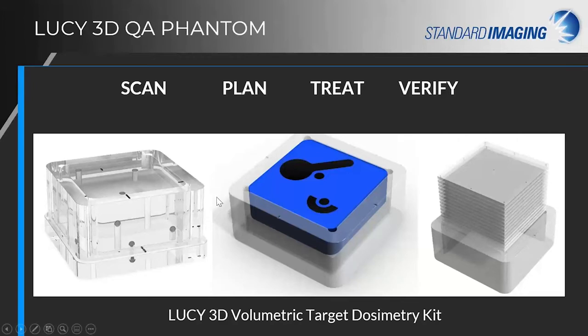One of the things that we do at Standard Imaging is look at what the challenges are on the market. We have customers, and OEM manufacturers such as BrainLab and Accuray or Varian Elekta have particular needs. For example, with the multi-mets insert, a customer says, hey, I want to use BrainLab's Elements software, but I don't know how to commission that. So let's develop a multi-METS insert. So this kit includes the multi-METS insert with film that you use to verify.